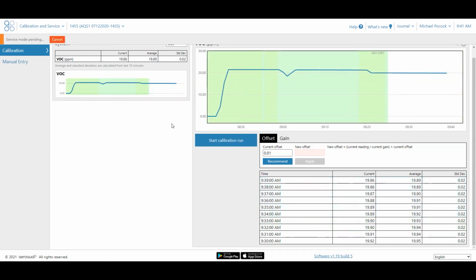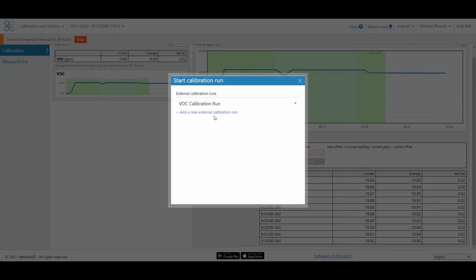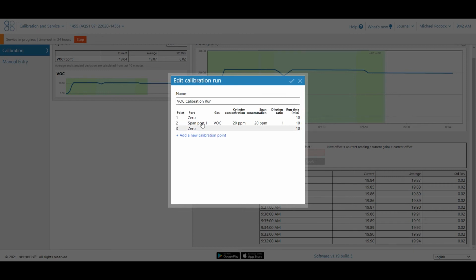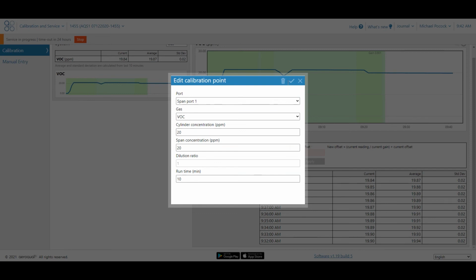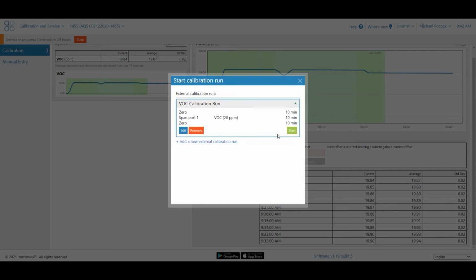Okay, so now we're going to look at the span calibration. So I'm just going to start this run again. We've done the zero. I've actually got a cylinder of 20 ppm VOCs of isobutylene. So we're going to use this cylinder with 20 ppm. So I changed that. You can edit here. Instead of using 10 ppm, we're using 20. So you can edit each of these points here. So now we'll start the calibration run again.